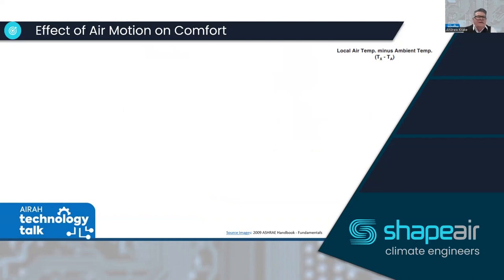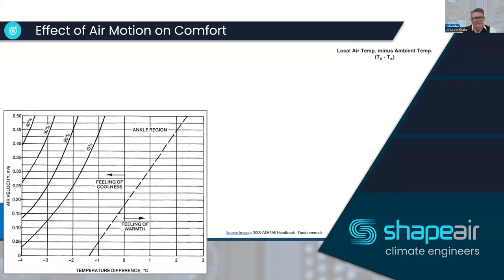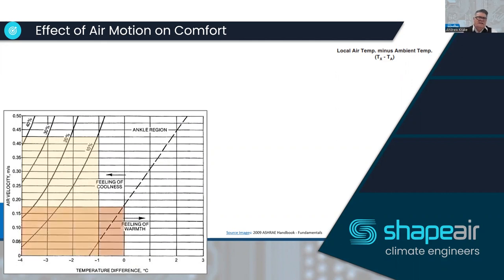Looking at the effects of air motion on comfort: this chart for the ankle region shows that with a velocity of 0.425 m/s and a one-degree temperature differential from ambient, 10% of people would be dissatisfied. If we simply reduce that velocity down to 0.18 m/s and we're on temperature, virtually no one in the space would be dissatisfied.